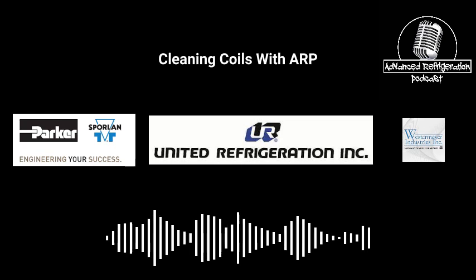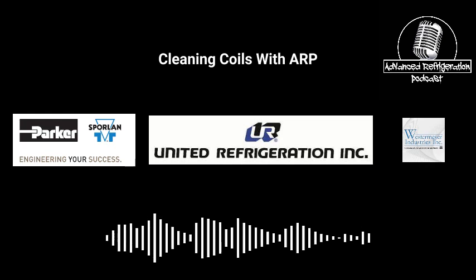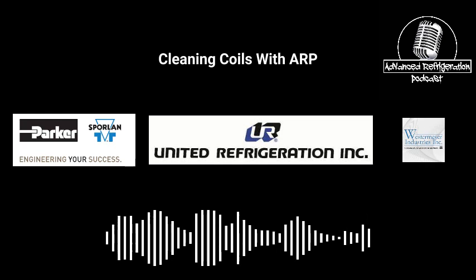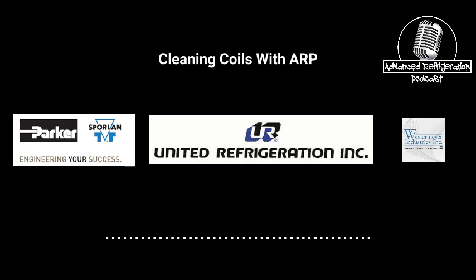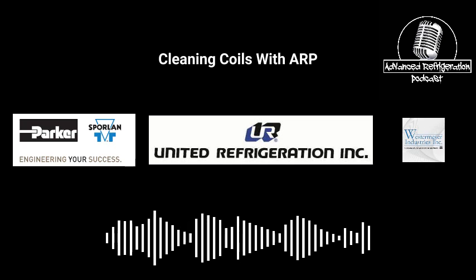I've seen racks where the condenser's plugged up and it's running 2 or 3 extra fans more than it needs in the middle of winter to maintain head pressure, because it's got a clogged condenser. And then we're running those motors harder the entire winter long, when we could have just cleaned it at the end of summer the second time and saved all that energy for the last 5 or 6 months. We missed out on all those energy savings because we're running the condenser harder than it needs to be.